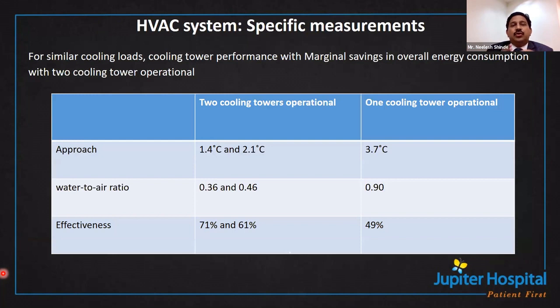Okay, now as I told you, the cooling tower also makes a difference. If two cooling towers are operational instead of one, you can see that effectiveness is 71 to 61% compared to 49% with one cooling tower. Normally we think, one chiller, so why have two cooling towers? But if you run two cooling towers and adjust the parameters properly, you can clearly see the effectiveness in the results.